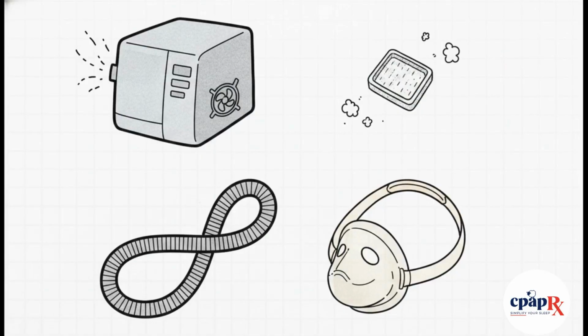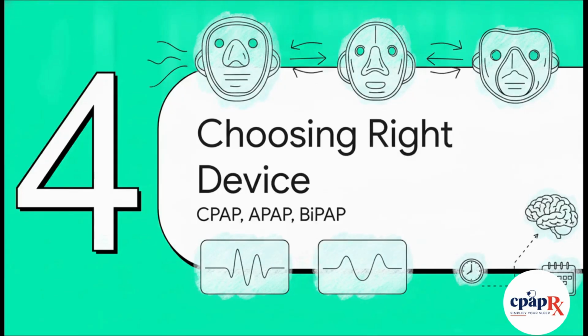To ground this in reality, the physical parts you interact with are super straightforward. Just be sure you aren't accidentally blocking the air intake on the main unit with a rogue pillow or blanket. Swap out that filter regularly, especially if you've got furry pets running around. Keep your tubing free from crazy twists, and aim for a mask fit that's secure, but definitely not painfully tight. We are going for comfort here. Which leads perfectly into Section 4, choosing the right device. We'll look at CPAP, APAP, and bipap.